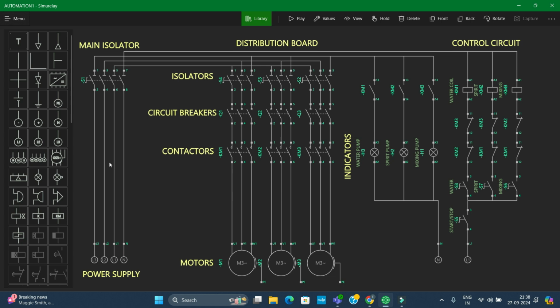So when I reach this point, this is my power supply - you can consider this as a bus, my busbar in the control panel. From there you get three wires connecting to your main isolator, the main switch. Then from there you have three different isolators rated depending on the motor you want to run. So this isolator corresponds to this motor here, and the same for the others - this is the line of isolators.